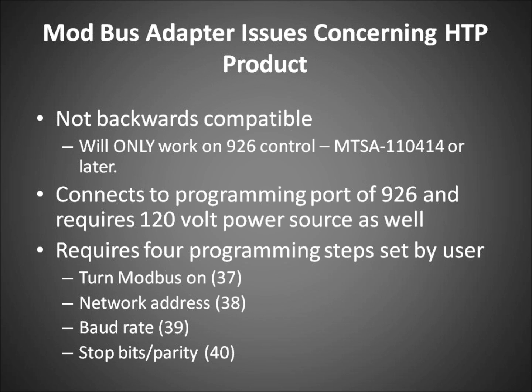Continuing on, the ModBus adapter issues concerning HTP products. One of the main things you have to know right up front is that this ModBus adapter is sensitive to the 926 control that we have on the main appliance. So it'll only work on 926 controls with a software revision, or a label on the transformer, of MTSA-110414 or later.